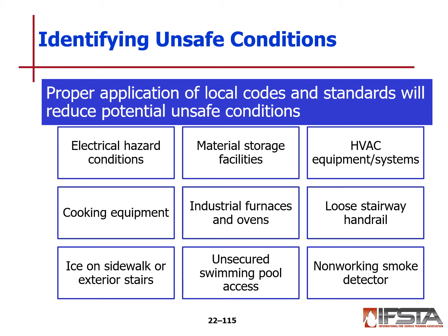Some of the things that we're looking for when it comes to the local codes and standards, our job is we note these to reduce potential unsafe conditions. And so we're looking for electrical hazard conditions. This could be improper wiring. This could be extension cords that are used for permanent wiring, which you see a lot. You might have breaker panels that are having problems that need to be repaired. Covers on electrical outlets and switches and panels.